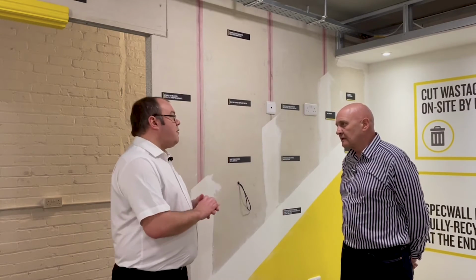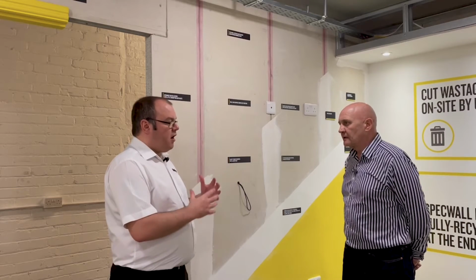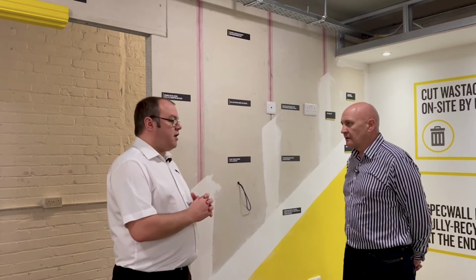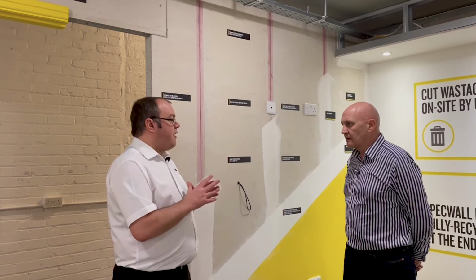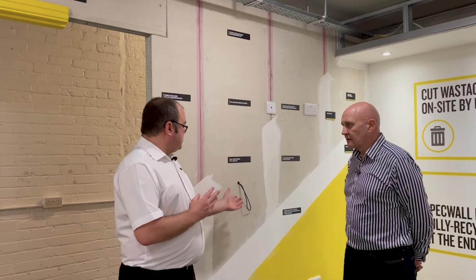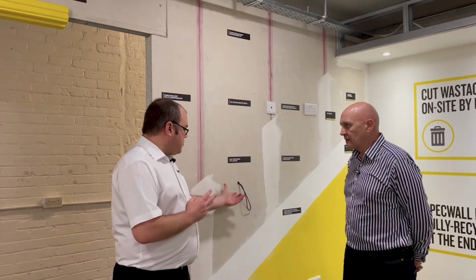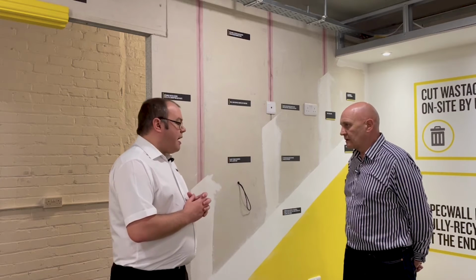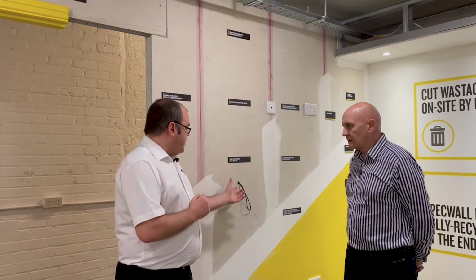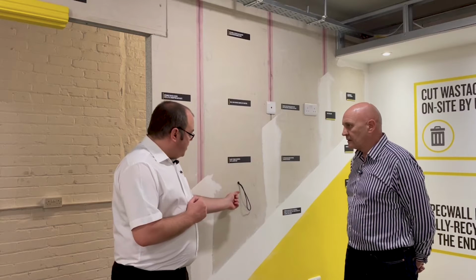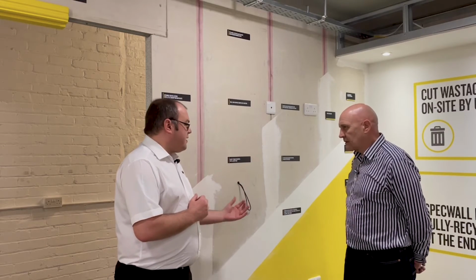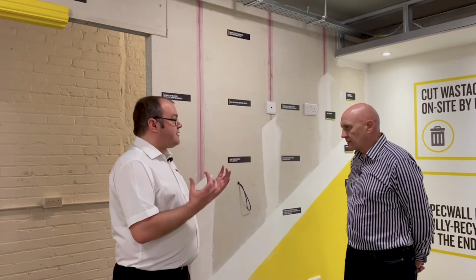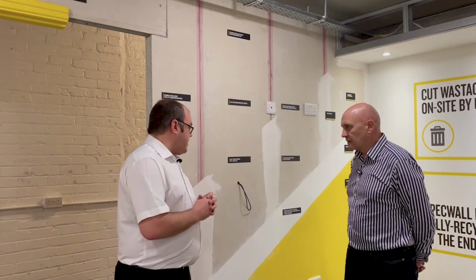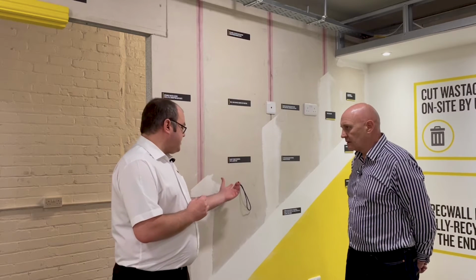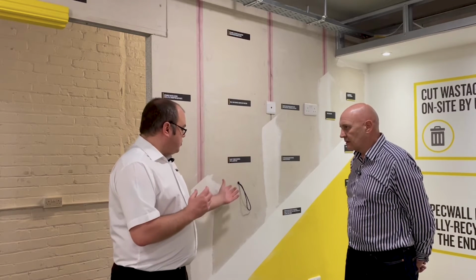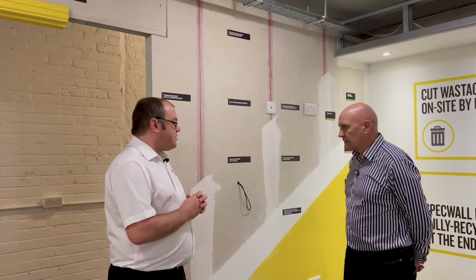Earlier on we looked at larger openings and larger service types, where you'd utilise the Quelstop fire batt as a pattress. But we also have solutions for single cables, small cable bundles, and small metal pipes like copper pipes, where you can do what's known as a direct-to-wall seal. Simply around the service you'd use our Quelstop acrylic sealant, and you'd have a tested fire resistant seal.